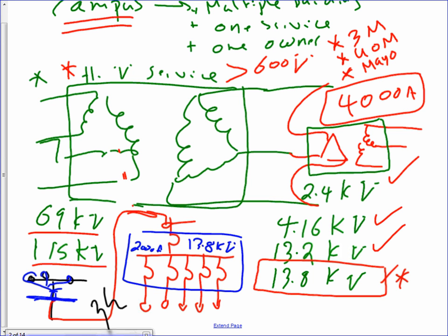You guys are not going to deal with it here with me, but that's a common practice. They can go up to 4,000 amp. They take the 13.8, guys, then transfer it down into 4,000 amp, 480/277. For example, in the Conduit building that I worked on, they take 13,800 volt cable through the building into the 13th floor, because nobody wants to sit on the 13th floor. And they have a big substation there, guys. You take the 13,800 volt through a fuse disconnect to a transformer, and you drop it down to 480 volt, 277, and they feed all the chillers and air handling units and what not. And then another substation, 208/120, and they feed all the receptacles and their lights, typically receptacles.